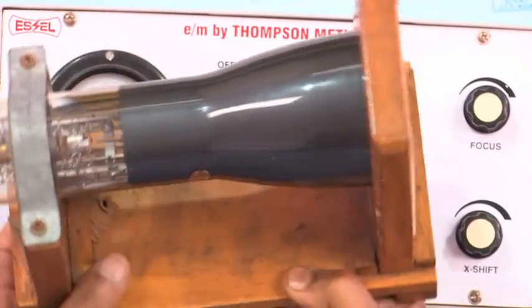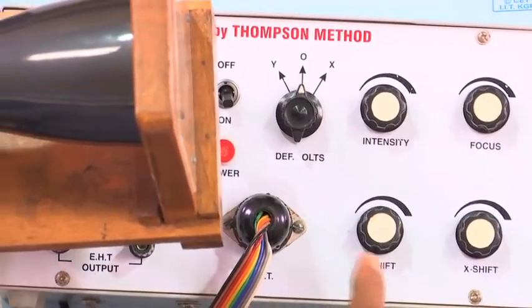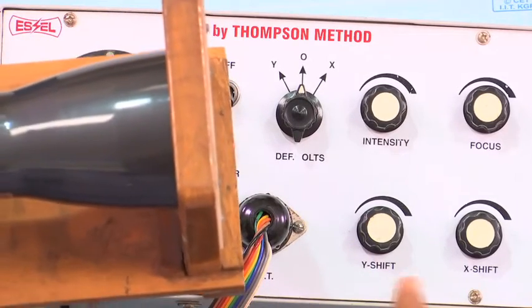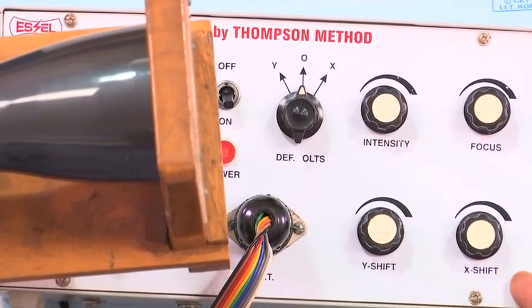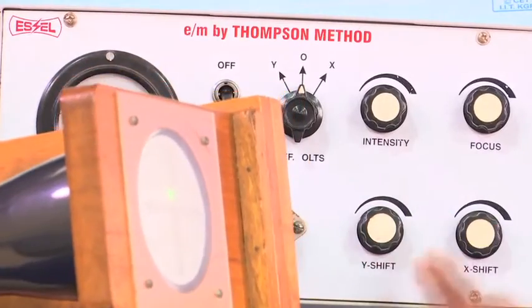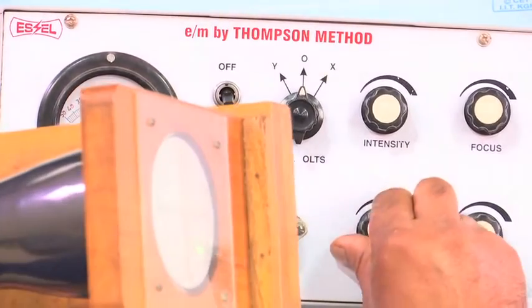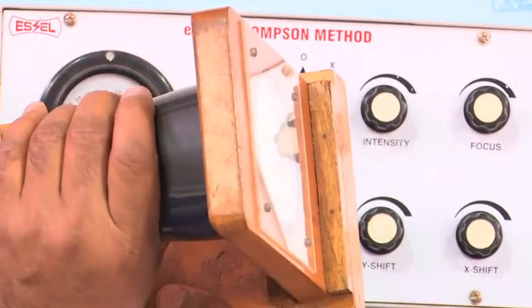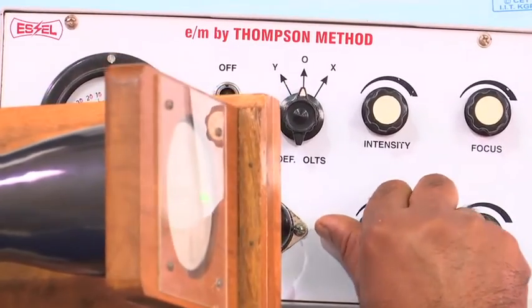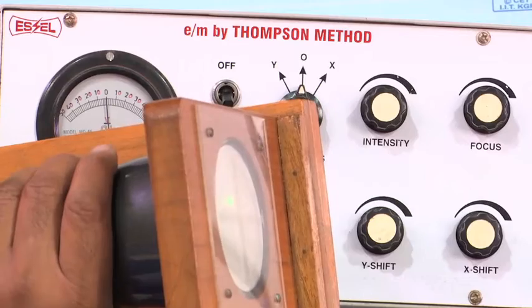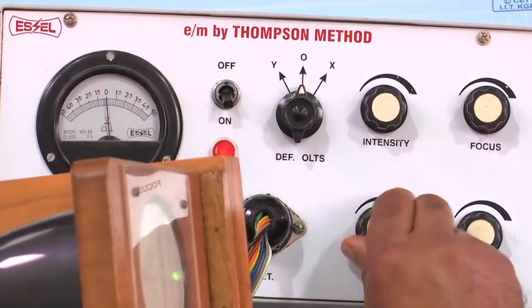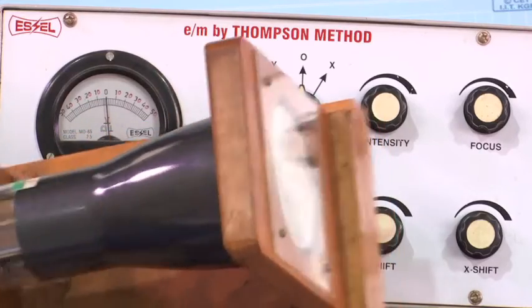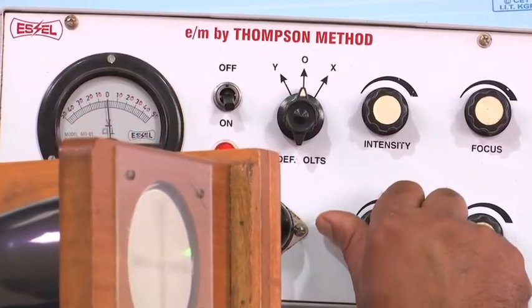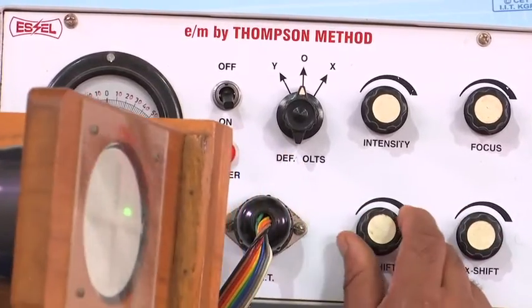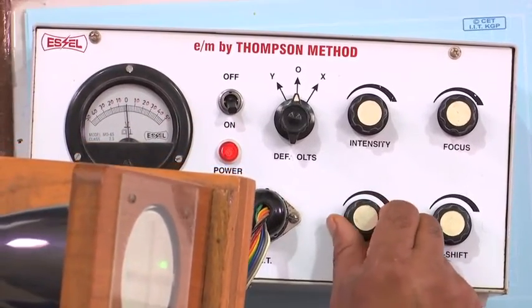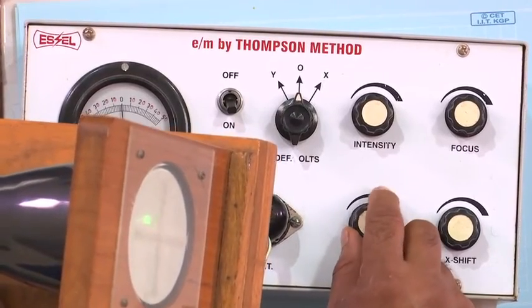So, y shift means voltage is given to the vertical plates, and x shift means voltage is given to the horizontal plates. So, I am changing this one. If I change, say it is y, it is going towards vertical, you see, but it is not quite. So, I have to rotate it, I guess. In the opposite direction, I have to rotate it to align with the scale. Yeah, now it is vertical more or less. So, when I am rotating this knob, I am just changing the voltage on the vertical plates.